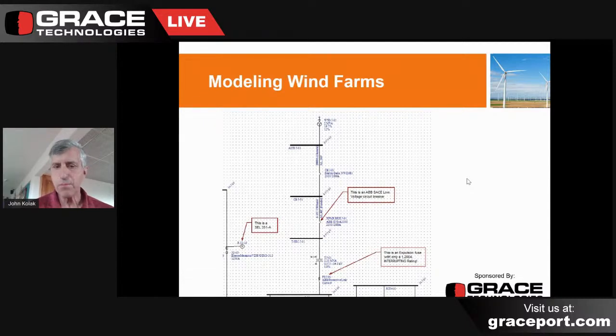You'll see that the ABB SACE breaker is usually our main circuit breaker on the wind turbine side. That's often labeled CB1 or Q1 in some vernacular. And then we have the low voltage windings all the way to the generator itself, where we have another breaker in the nacelle and then the generator itself. And once again, getting the fault current from the generator from the manufacturer is normally what we recommend. But otherwise, you can just simply do a short circuit calculation to get your bolted fault current. And then using the formulas in the 1584, you can produce arcing current and use that if needed. But again, normally we model that just as an induction generator, and that gives us a pretty good rendition of short circuit current on that part of the farm.